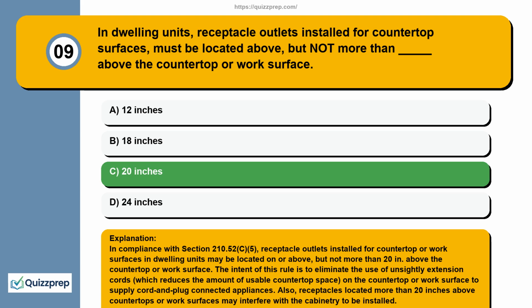The intent of this rule is to eliminate the use of unsightly extension cords, which reduces the amount of usable countertop space on the countertop or work surface to supply cord-and-plug connected appliances. Also, receptacles located more than 20 inches above countertops or work surfaces may interfere with the cabinetry to be installed.